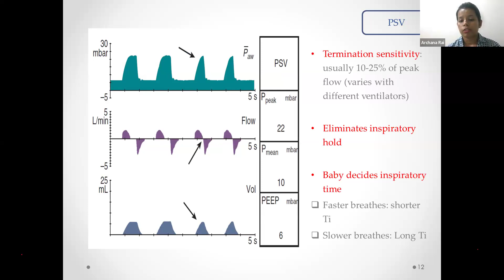So the advantages of PSV mode are that all the breaths are supported, like assist control or the SIPPV mode. There will be inspiratory synchrony like SIMV mode and assist control modes, and there will also be expiratory synchrony. That is the advantage of the PSV mode over the other pressure triggered modes. Because of this, there will be less fluctuation in the intrathoracic and intracranial pressure, so there is less chance of IVH. And PSV can be used as a standalone mode, or it can be combined with the SIMV mode.